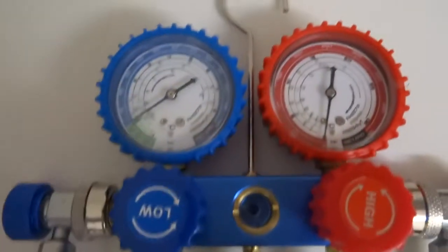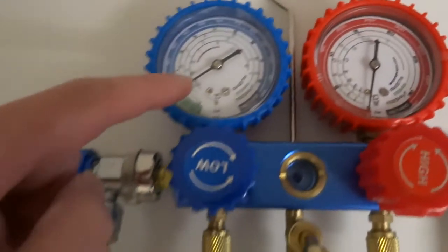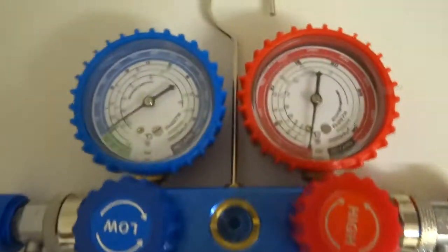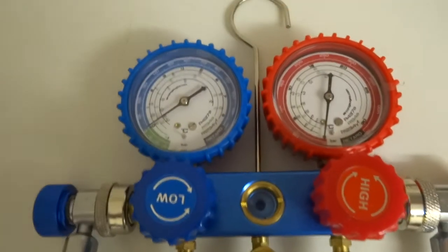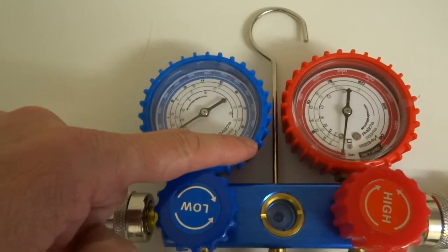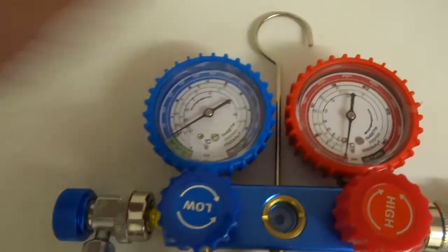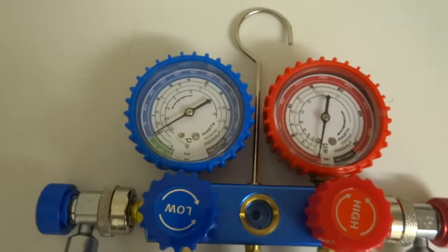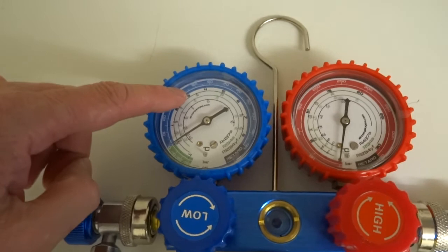So basically the gauges, you have a pressure reading on the outside. This is the low side, high side. This one goes up to 120 psi. This one goes up to 450. Basically a good reading would be about 35 to 40 and about 200 on this side.